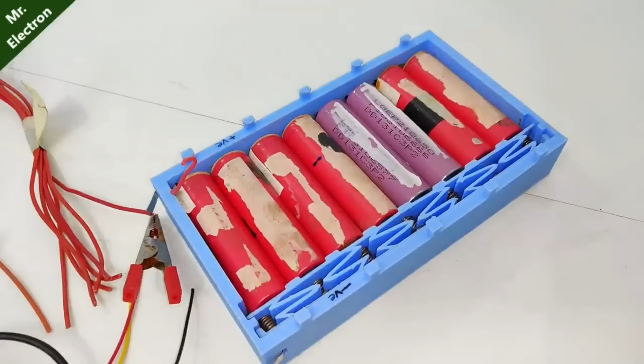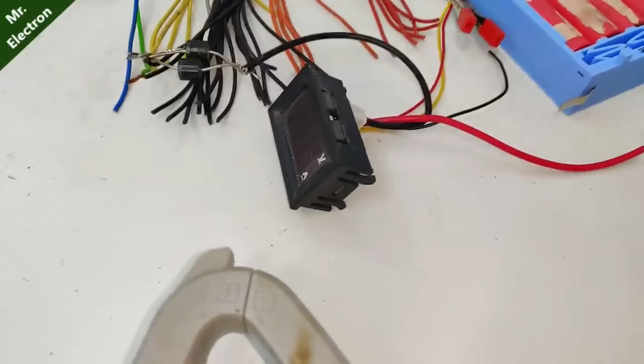So I have to repeat the process with the rest of the batteries. Now guys, I've placed another set of dead batteries this time. Okay, and that's the meter, it's still not on. So here, as you can see, the open circuit voltage. Now let's connect positive and the negative. You can see the meter just turned off because the voltage of the batteries is so low that it cannot even operate. The voltage from the power supply has dropped to the level of the battery, because of which this is getting a voltage less than the rated, and now we are close to it.